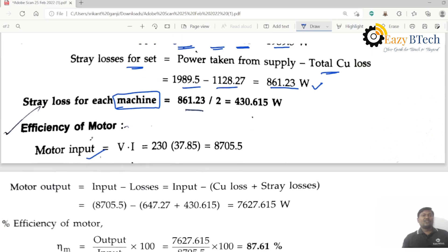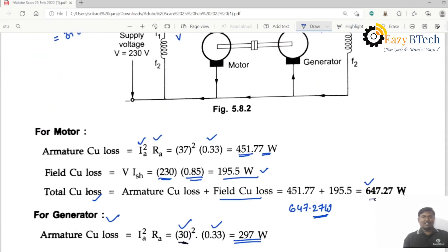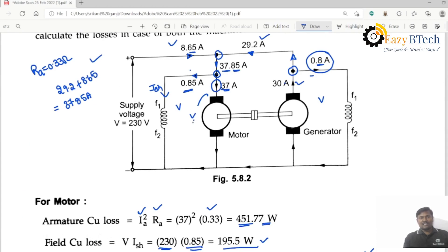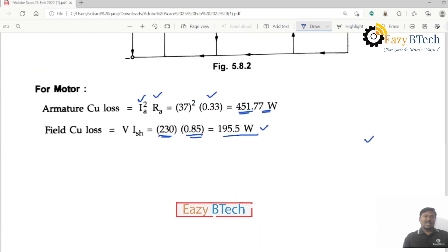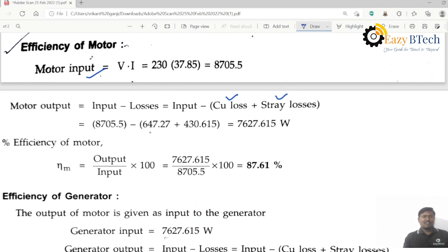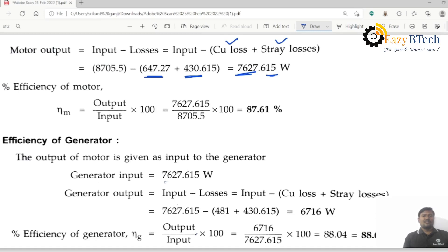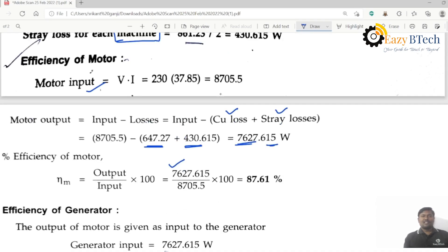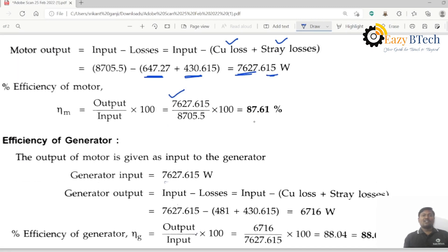The motor input power is V into I, where the armature current is 37 amperes. From that we subtract the losses — copper loss plus stray losses: 647.27 plus 430.615 — giving the motor output of 7627.615 watts. The efficiency of the motor is output power divided by input power into 100. Input power is 8705.5 watts, giving an efficiency of 87.61%.